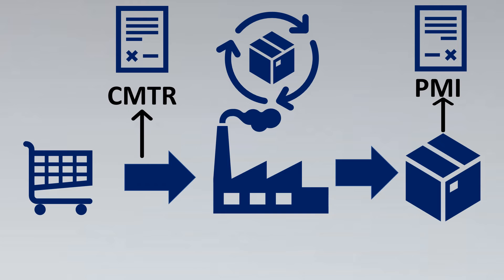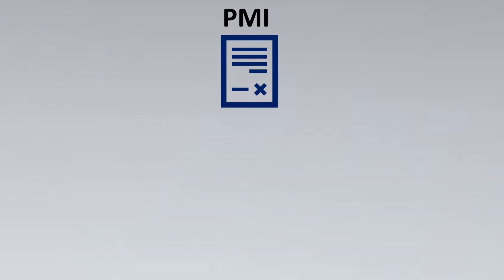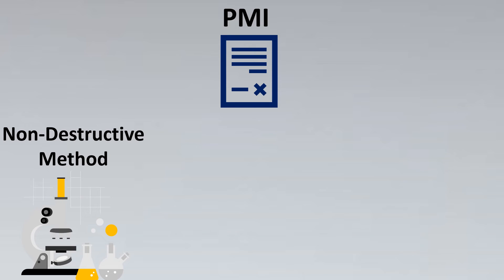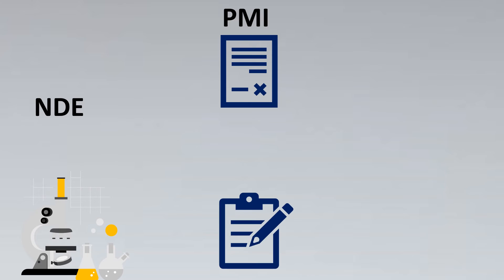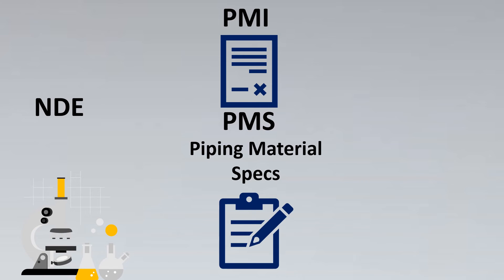Now let's look into PMI — what it actually means and when to use it. PMI, in short and simple terms, is a non-destructive method of testing a particular material composition, called NDE for short. One basis for when to use PMI is the piping material spec (PMS) of a particular pipe. If a pipe material specification requires PMI, then obviously the instrument department also has to take PMI into consideration, because if piping is taking it, the instrument also needs to go through PMI.